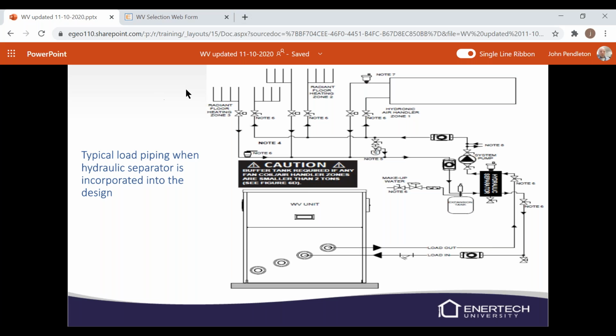Here we've got 3 radiant zones and an air handler. That's that box right by where it says note 7. So these radiant zones may not take all the flow that you need. So this hydraulic separator will allow the unit to still see its proper flow and not really worry too much about what the zones flow. We also do recommend putting an automatic air vent in the highest point of the system to eliminate any micro bubbles or air in the system as well.